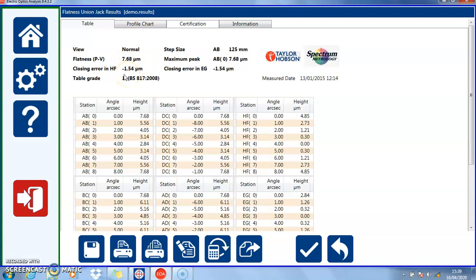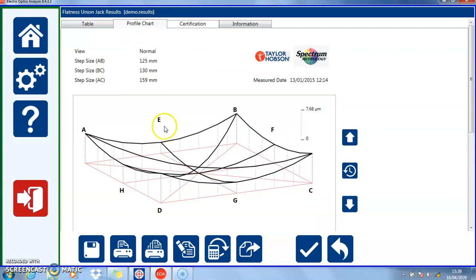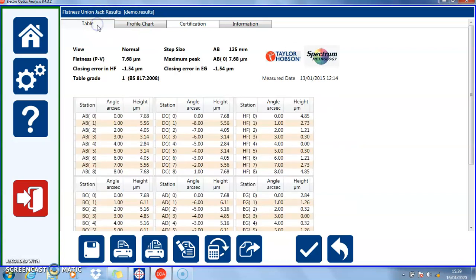This is the height difference between, I'll show you on the chart, this line and this line. It should be taken into consideration. This should really be less than 10% of the total peak to valley, and it shows how good the integrity of the measurement is. If this is larger than 10%, something has possibly gone wrong and should be reanalyzed.